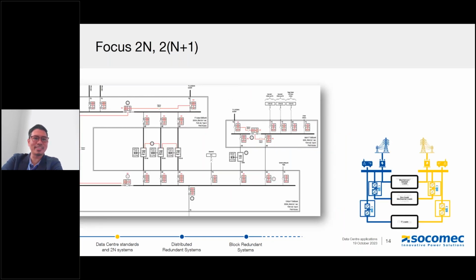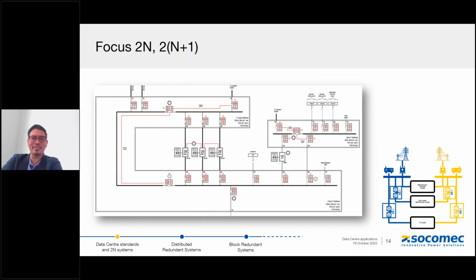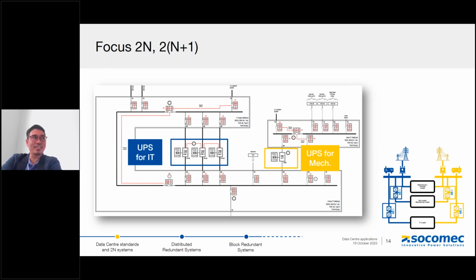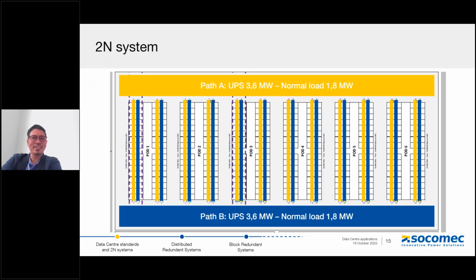Here's an example of a single line diagram of a 2N solution with a distributed architecture. You can see a separate UPS for our IT load, and of course we have a UPS for our mechanical load, as you can see here. If you go to the data hall, you have your two systems. Just a review: you have your A source and B source, which will be powering the system. As you can see here, as an example, you have a 3.6 megawatt power pack. Both of them are running at half load, or 50%. So if one of those sources fails, the other one will be able to handle the rest. So it's typical 2N, right?